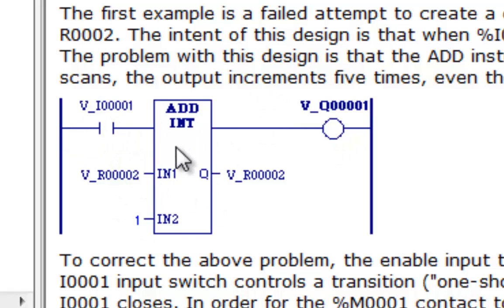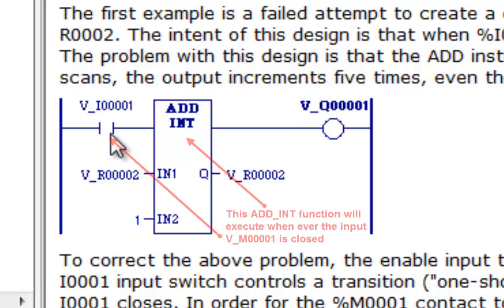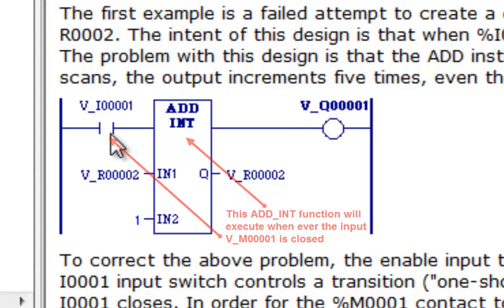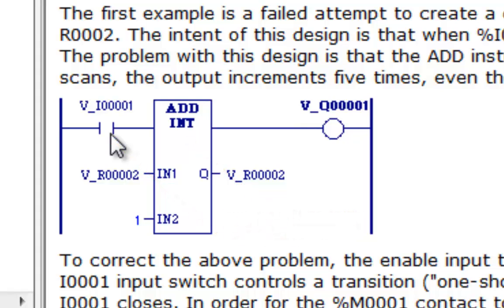Now what you'll find is that this executes every time for each scan that the controller is operating through, just as long as this is closed. So if you have a push button and you close that push button for, say, three seconds, it will continue to add for the entire time that that contact is closed. I've got some examples, and I'll show you what I'm talking about here.